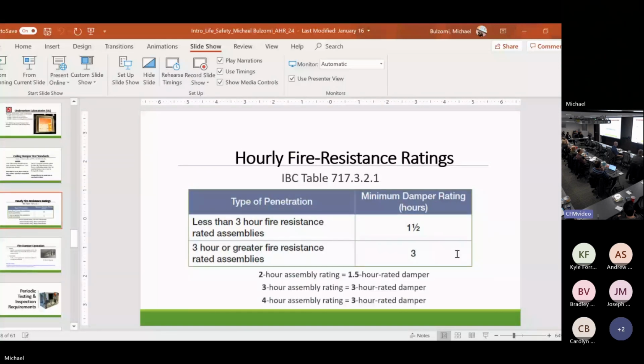All right, fire resistance ratings. Again, we're in the International Building Code. This is where we determine what the rating requirements are for my fire dampers and fire smoke dampers. Real simple: if my barrier is less than 3 hour fire resistance rated, I use an hour and a half damper. If my barrier is 3 hours or greater, I use a 3 hour damper. So there are 2 hour assemblies, 1 hour assemblies, 4 hour assemblies. If I have a 2 hour assembly, I use an hour and a half damper.